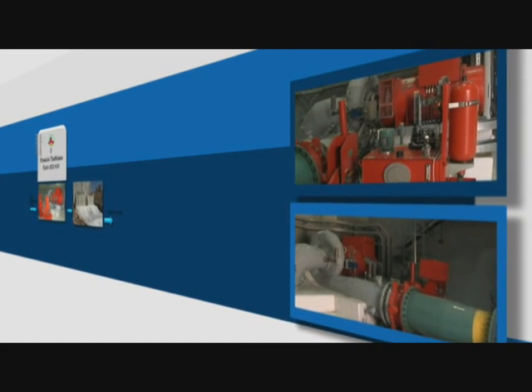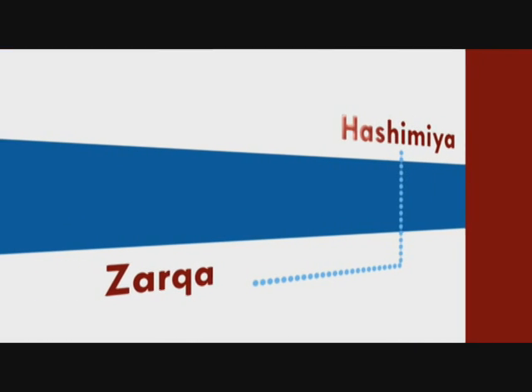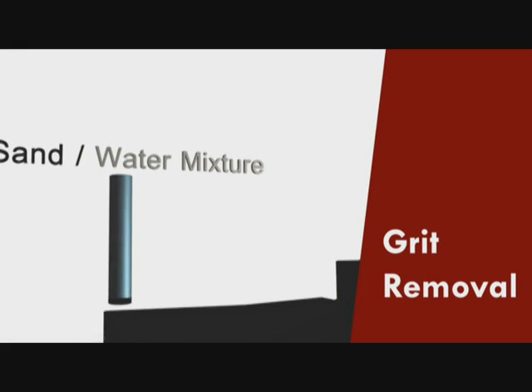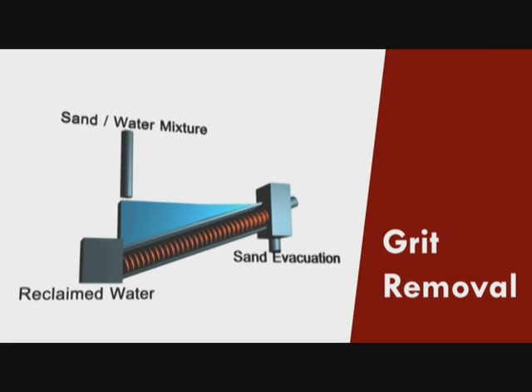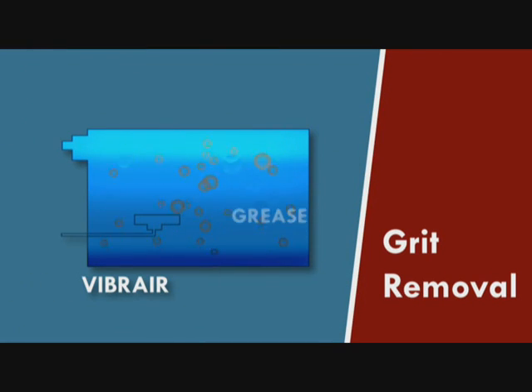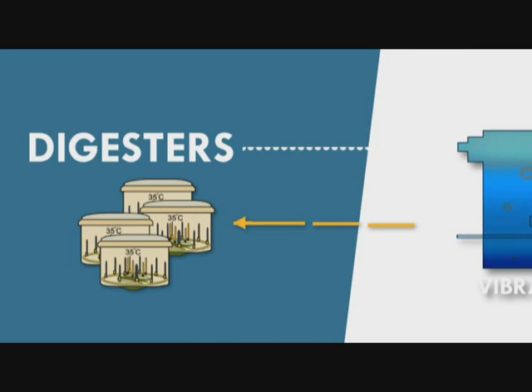The outlet joins the incoming wastewater from the Zarqa and Hashemiya pumping stations and is distributed into two grit and sulfide removal tanks. Air is introduced at the bottom of the grit chamber causing heavy particles to settle, which are collected by a screw and then discharged into a grit classifier. Air bubbles cause oil, grease, and scum to float to the surface, which is then collected in a scum pit and pumped to the digesters.